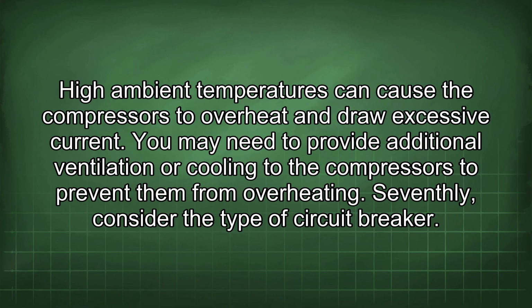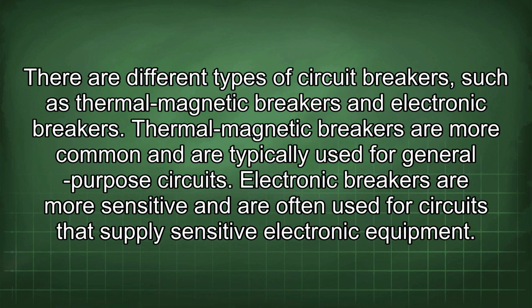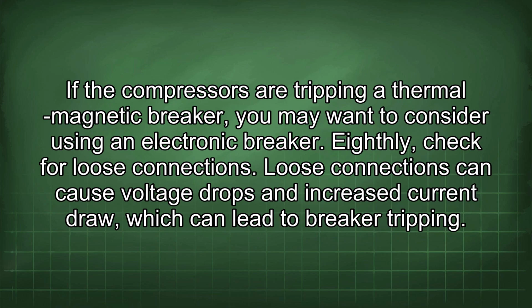Seventhly, consider the type of circuit breaker. There are different types of circuit breakers, such as thermal magnetic breakers and electronic breakers. Thermal magnetic breakers are more common and are typically used for general purpose circuits. Electronic breakers are more sensitive and are often used for circuits that supply sensitive electronic equipment. If the compressors are tripping a thermal magnetic breaker, you may want to consider using an electronic breaker.